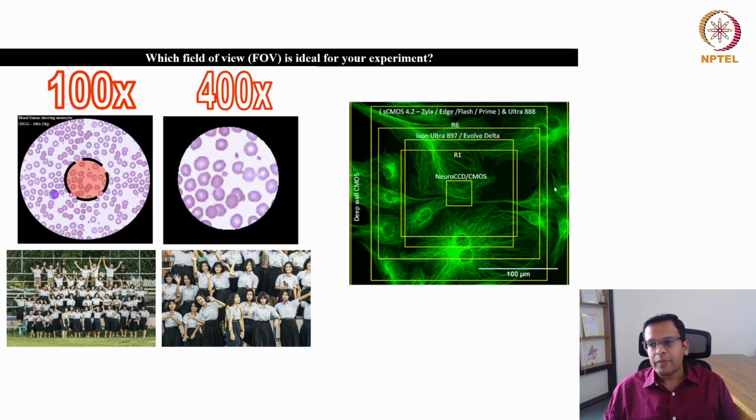members. Different companies manufacture this camera with different fields of view. Here you can see which fields of view some of the companies offer. While procuring the microscope, you should take care of this field of view before ordering the camera, because if you go for a camera with a very small field of view and for some applications you need a bigger field of view, it is not possible. So consider this parameter while procuring a new camera or a new microscope.